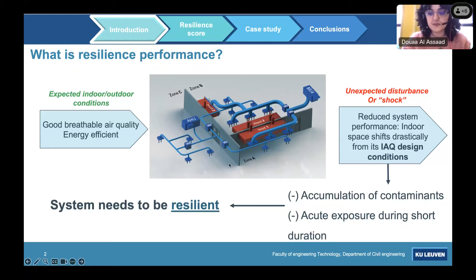I also talked to you in the beginning about disruptive events. So how can we classify these disruptive events? First, we have mechanical disruptions that occur to the components of the ventilation systems and that can cause a partial or complete disruption in the operation of the system. This can be due to a lack of preventive maintenance or inadequate fault diagnostics techniques. For example, this can be fan failures, power outages, or fouling filters.